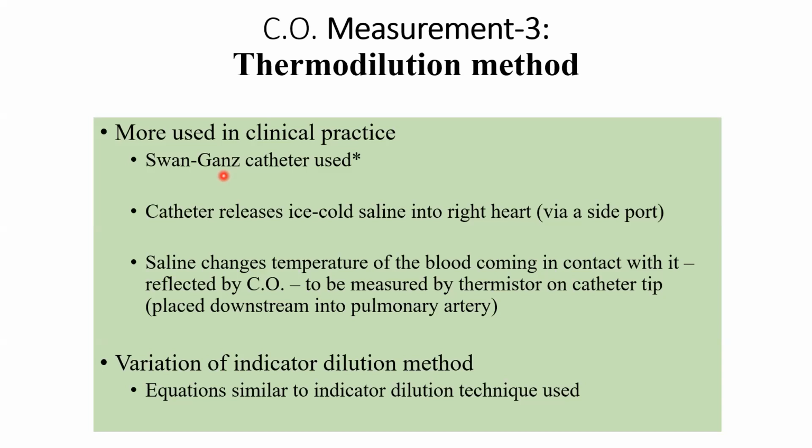And just before the tip on the side, there is a way to introduce something inside wherever you put this catheter in. It's like a pocket or an opening, right? And so that's one feature of this tube. And right at the tip of this tube, you have a thermistor. You have a temperature sensing sensor.